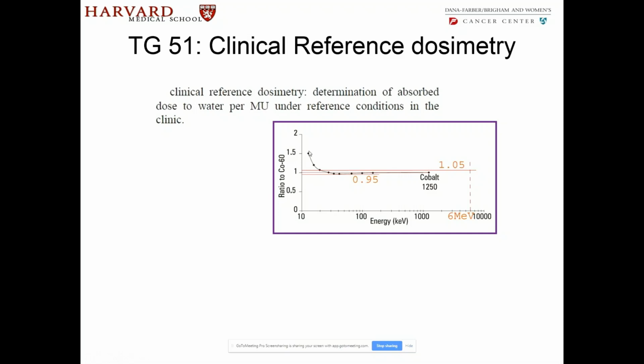Now, the problem is it stops at cobalt. Your machine is, let's say, at energy 6 MV. Well, there's no curve there to begin with. I have drawn tangents here to the lowest value that it goes, and that turns out to be about 0.95. So this is 5% lower. And symmetrically, if you go, it's about 5% higher. So those are the two lines that I've drawn. Let's say this curve keeps going up. Looking at this, if you did not do anything to your ion chamber, chances are you will be off by 5%.